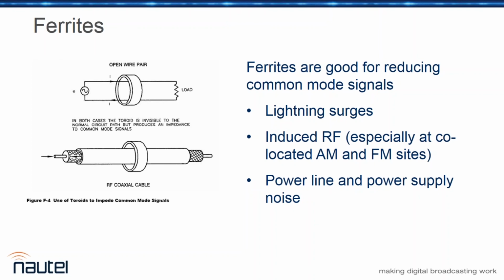Well, we routinely install them on any audio and remote control to a transmitter. We had a site long ago here in Louisiana where they decided to move the studios back to the transmitter site to save money in the building. It's just a little 1 kilowatt AM, but the shunt-fed tower is about 10 feet behind the back of the building, so they've got relatively modern studios in there, and there was RF on everything - literally everything, the phones, the computers, the audio, the mics, everything. We ran around with a bunch of little ferrites and wound 2 or 3 turns to each ferrite, and that got rid of about 90% of the RF right there without doing anything else.